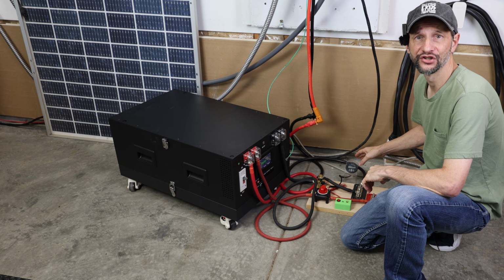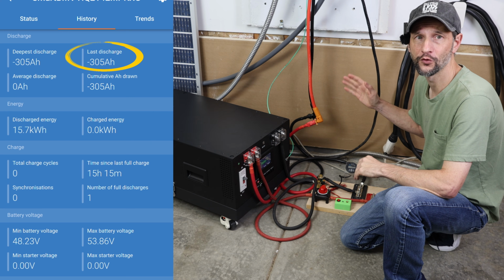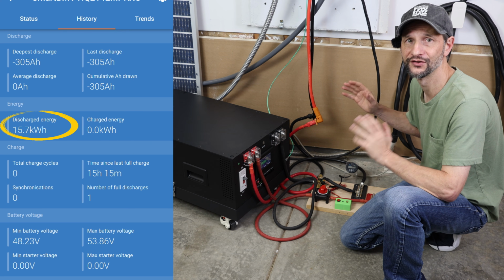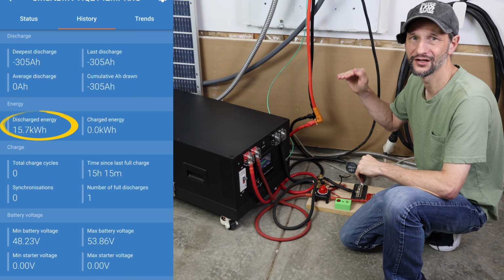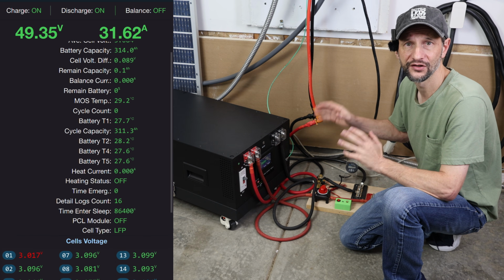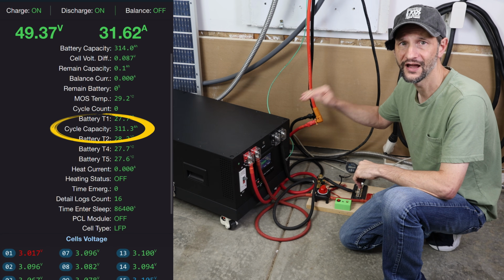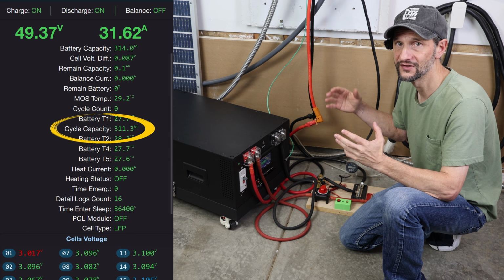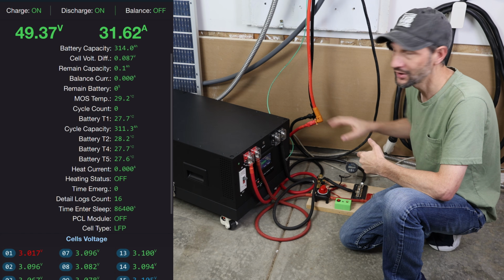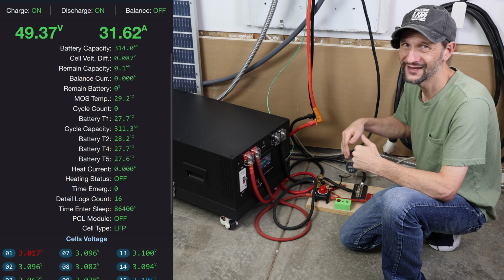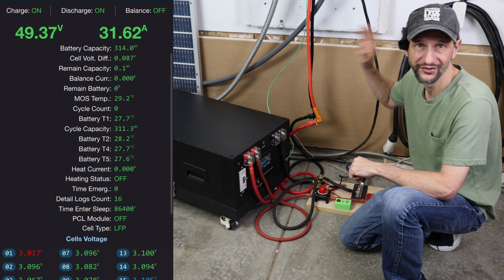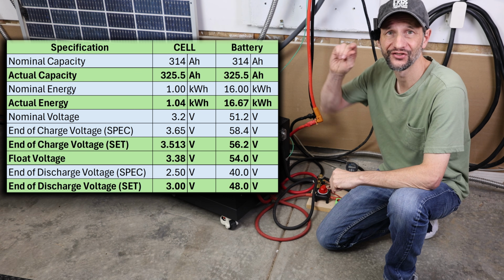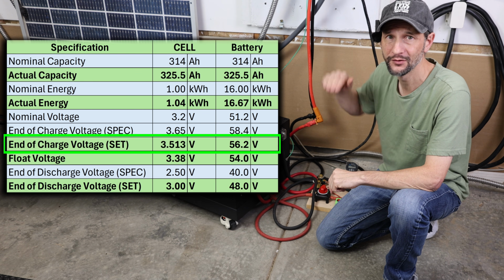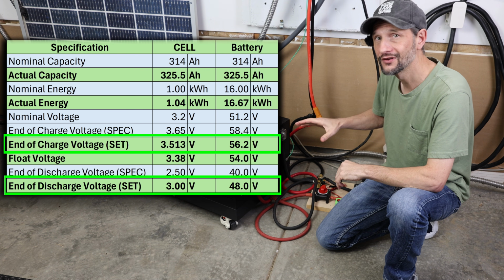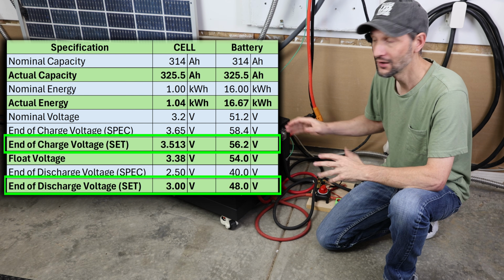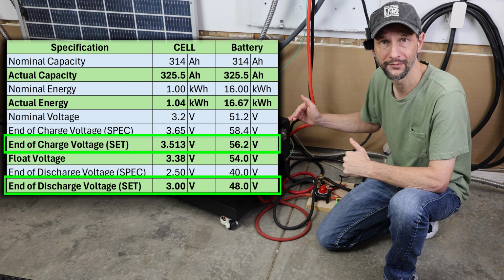The Victron shunt shows 305 amp hours, or 15.7 kilowatt hours discharged, just shy of the 16 kilowatt hour full capacity. The BMS shows a cycle capacity a little bit higher, at 311 amp hours, which is even closer to the full capacity. So with a couple different sources, you can see we'll get more than 15 kilowatt hours using these settings. You can also see how just a slight adjustment in the max charge voltage and minimum discharge voltage will allow us to utilize 95% of the battery capacity while dramatically reducing the cycle stress on the battery.